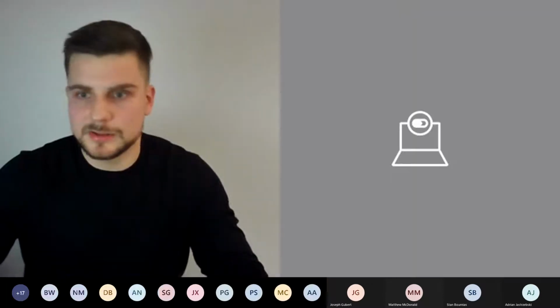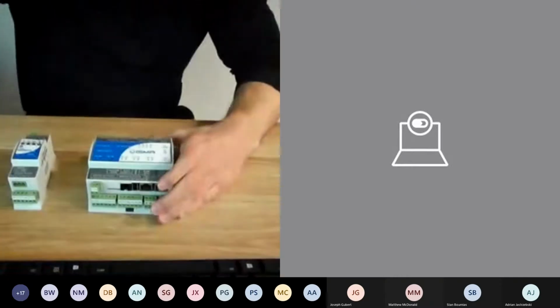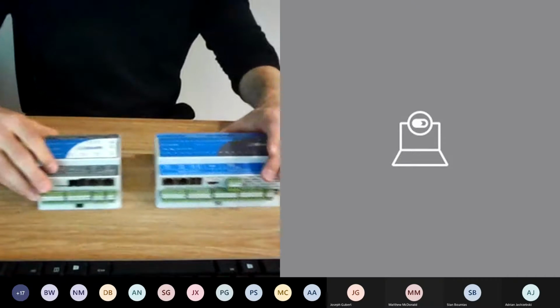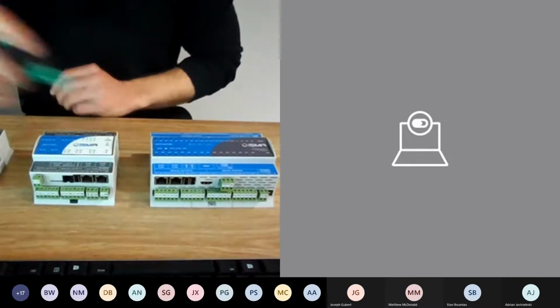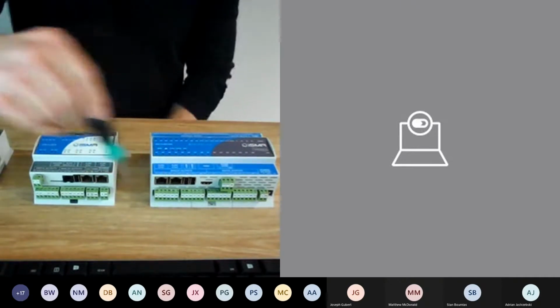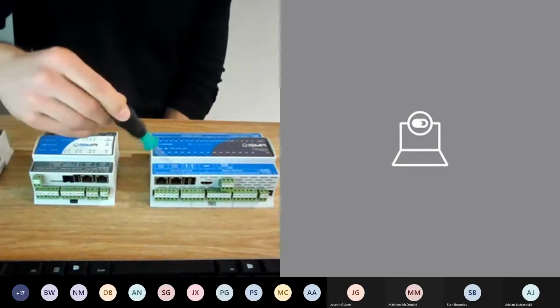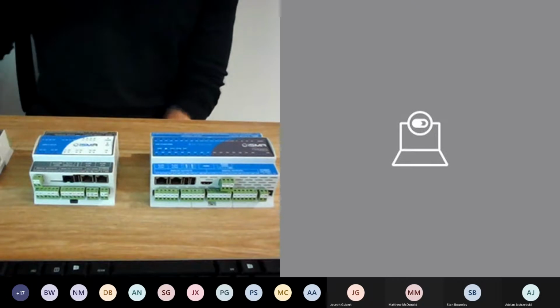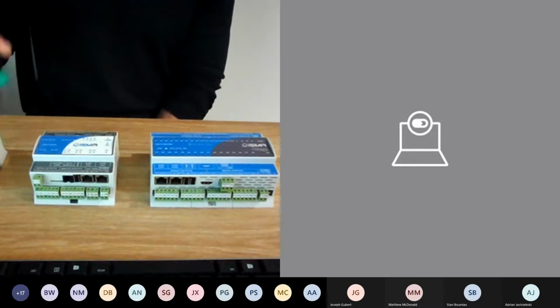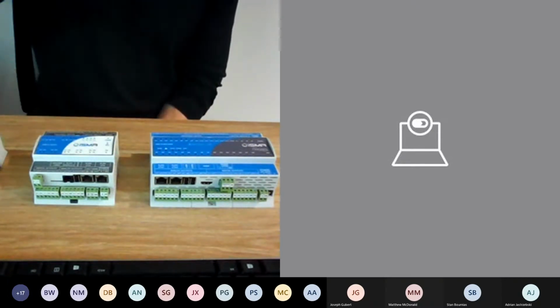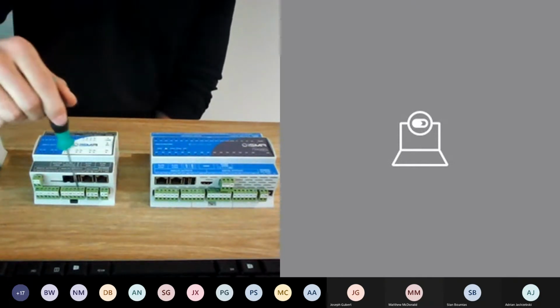Now, the second part of this first section, which is about the MIX IP modules. So we also support BACnet IP and Modbus TCP. Before we go to this section, I will also talk a little bit about the modules themselves, because right now the configuration will look like this: we have a connection between Mac36 and Mix18 through the Ethernet interface, through the IP protocol, and then we are going to connect these RS485 modules here to the Mix18. This way we'll be able to get to this RS485 module through the Modbus TCP network.